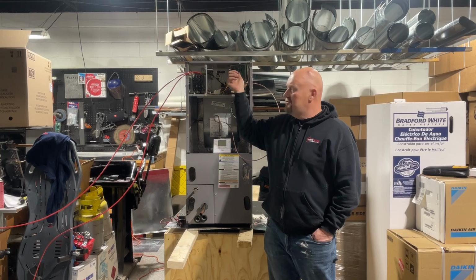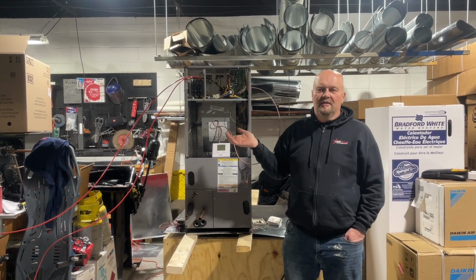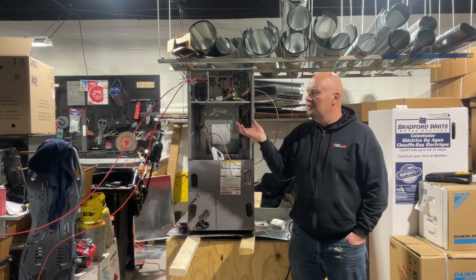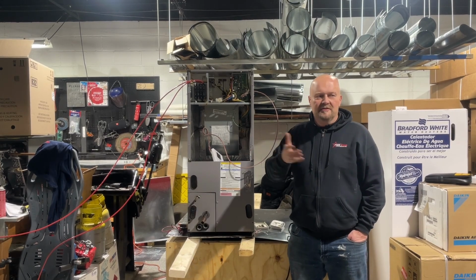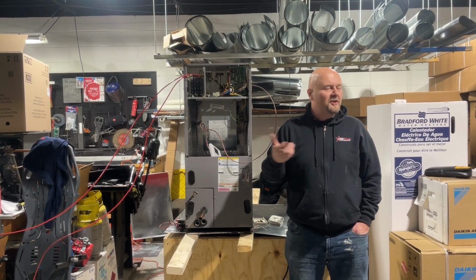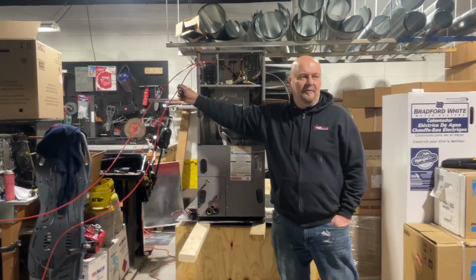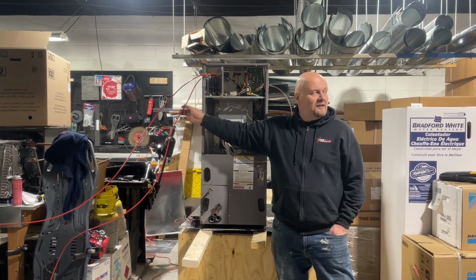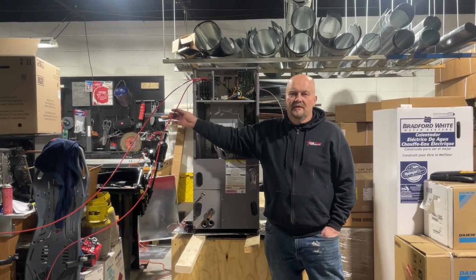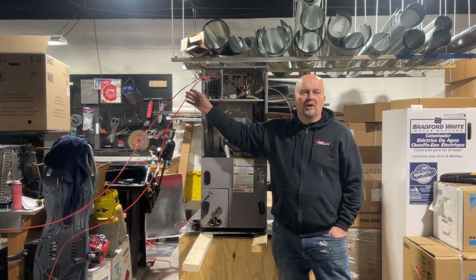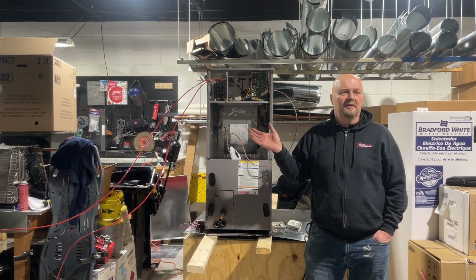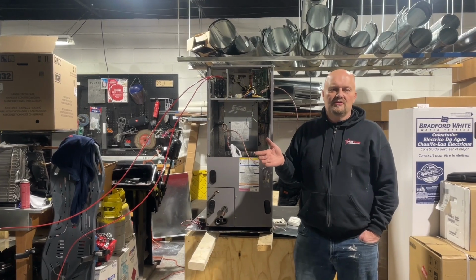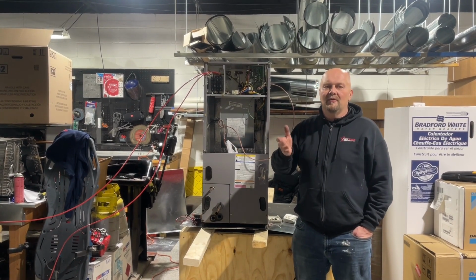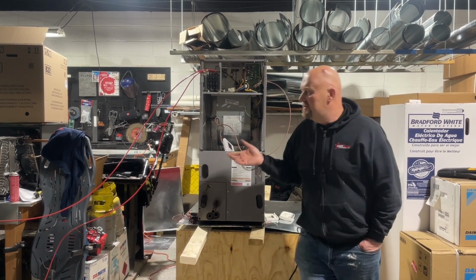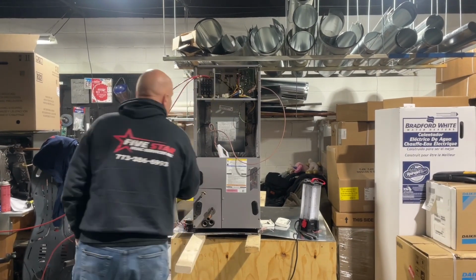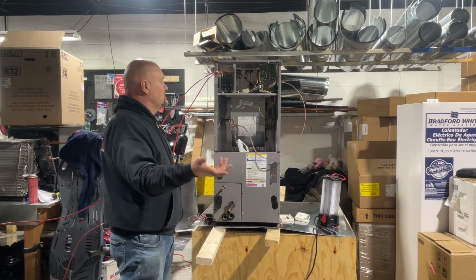This probably can actually do that inside the computer control board. So electrically, these furnaces are very easy. As long as you remember that the information you're going to get is using an amp clamp. Remember that. You cannot diagnose an electric furnace without an amp clamp. Knowing the voltage isn't going to be enough. You're blind. You don't know where it's drawing, you don't know how much it's taking. This will tell us how much is going in there, what BTUs we're getting. Is that what it's supposed to be?